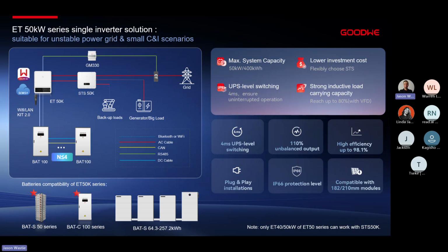There we can have up to a 500 kilowatt, 4 megawatt hour plant when we're using our BAT 100, the 100 kilowatt hour outdoor battery cabinet. With the BAT S50 series, the 56 kilowatt hour battery stack, we can connect up to 6 of these together in parallel onto one inverter, meaning we can go 500 kilowatts, 3.6 megawatt hours of battery connections with the BAT S50 series.